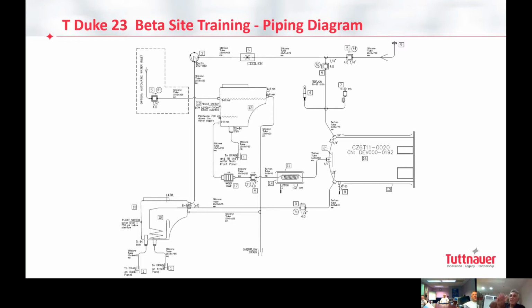These are membranes. It's not a piston. You know the difference between piston and membrane. A piston is long with a small diameter. This is short with a big diameter. So if I place something, any molecule, if it's not gas, between the membrane, it will get damaged. Even though we are trying to suck from the top of the chamber into the pump, because of the chiller you get some bubbles of water. So slowly, after some time, you observe some water between the membrane, right?